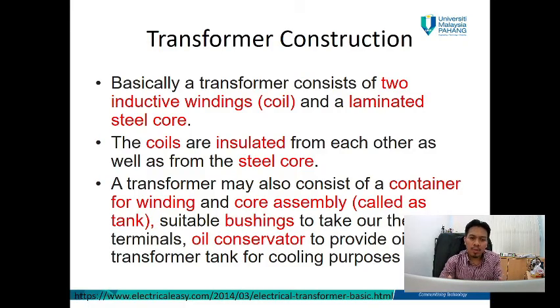The basic transformer construction consists of two windings, primary and secondary, and also a laminated steel core. The coil or winding is insulated from each other, as well as from the steel core. A transformer also consists of a container for the winding and core assembly, which we call the tank, and also a bushing for terminal connectivity, and an oil conservator to provide oil in the transformer for cooling purposes.